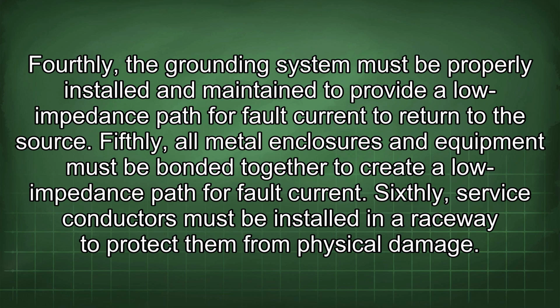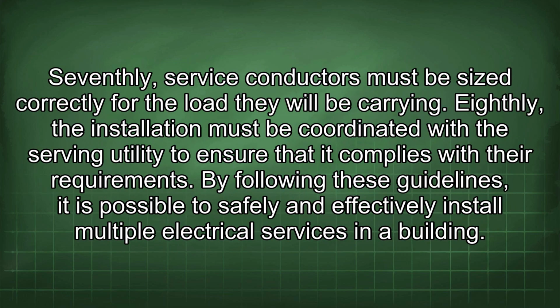Fifthly, all metal enclosures and equipment must be bonded together to create a low impedance path for fault current. Sixthly, service conductors must be installed in a raceway to protect them from physical damage. Seventhly, service conductors must be sized correctly for the load they will be carrying. Eighthly, the installation must be coordinated with the serving utility to ensure that it complies with their requirements. By following these guidelines, it is possible to safely and effectively install multiple electrical services in a building.